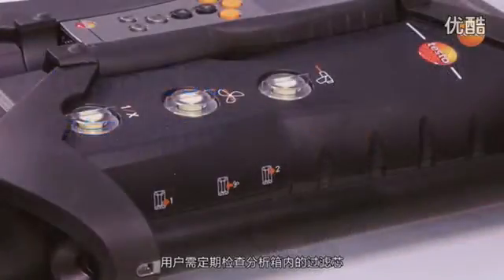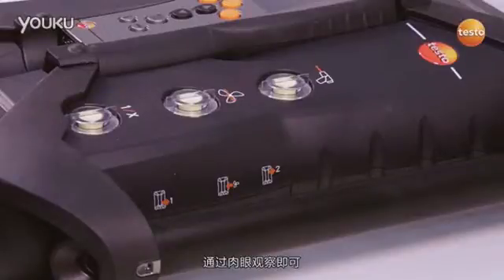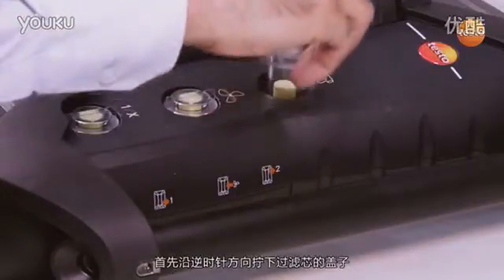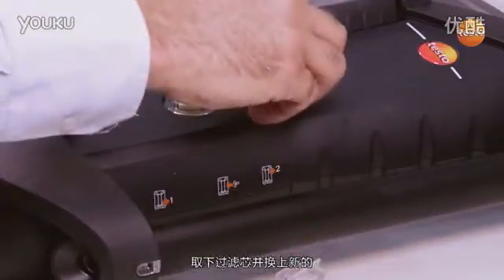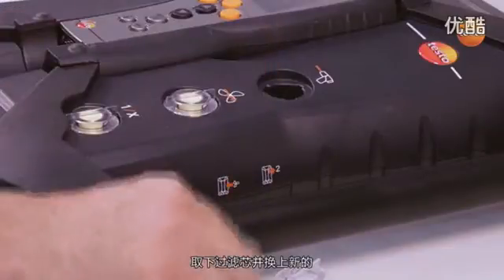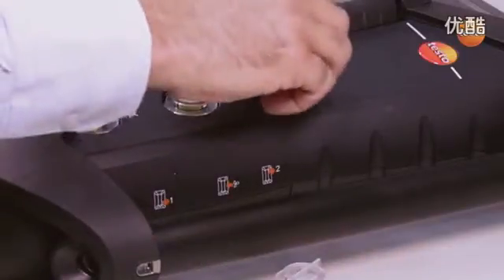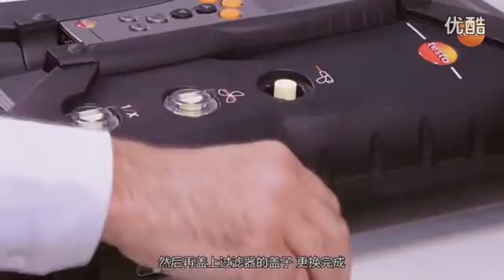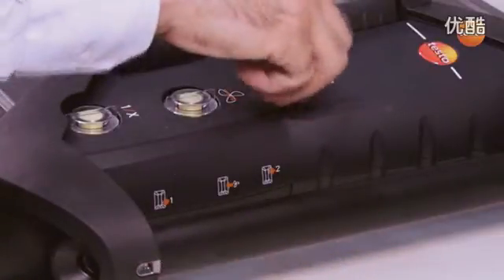The dirt filters in the analyzer box should be regularly checked for dirt. A visual check in the sight window is enough. If there is dirt visible, the filters must be replaced. To open the filter chamber, I turn the filter cover anti-clockwise, remove the dirt filter and replace it with a new filter. I then lock the filter cover again.